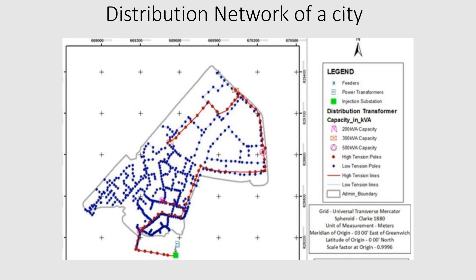This is a typical distribution network of a city. The blue poles are low-tension poles and the red ones are high-tension poles. If a small solar or wind power plant wants to connect to the nearest grid, they will request the distribution company for a grant of connectivity. The company will check all these small substations and feeders for any available injection capability, and if available, will grant connectivity.